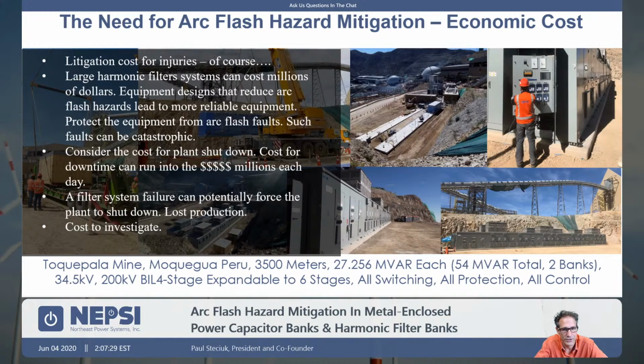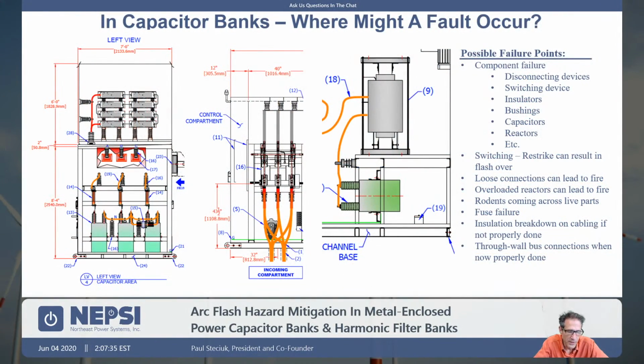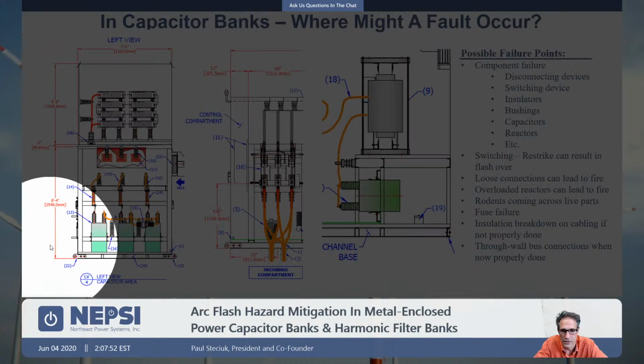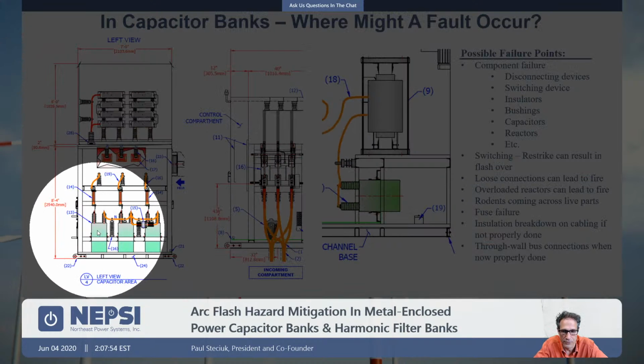Arc flash mitigation is about trying to prevent the failures in the first place if possible. So I start off with this very simple set of drawings of some metal enclosed systems, and I ask the question, where might a fault occur within a metal enclosed capacitor bank or harmonic filter bank? And I would start to point out some things. If you just think about it, you have the capacitors themselves. If the capacitors fail, it's a fault point.